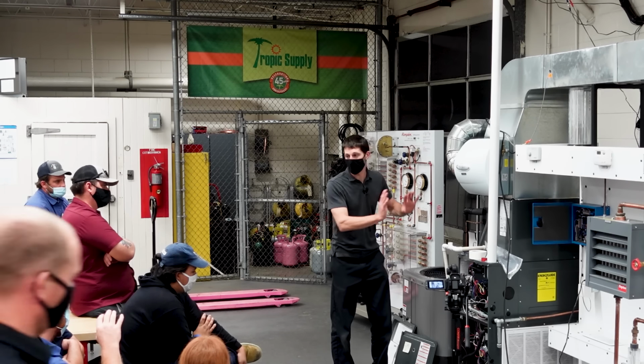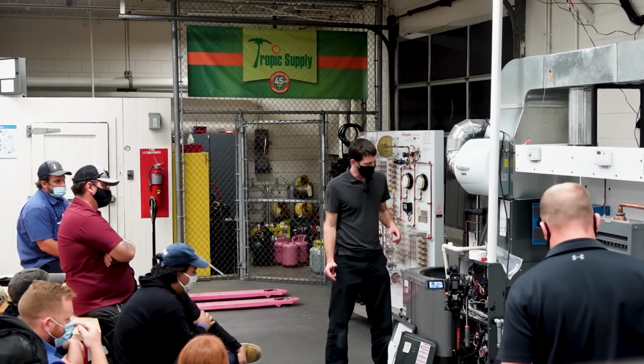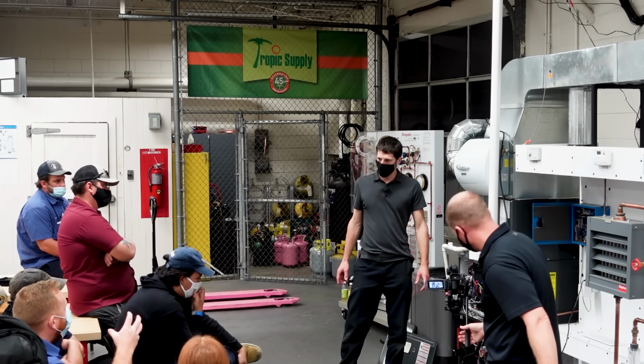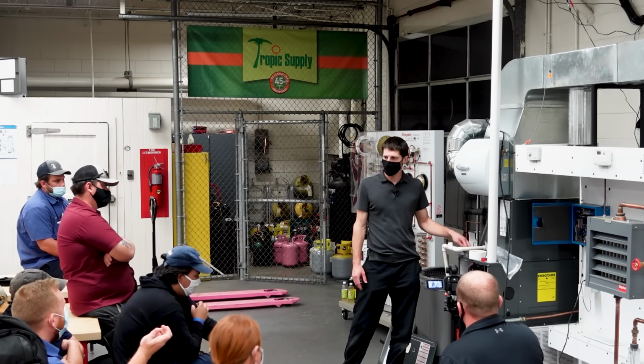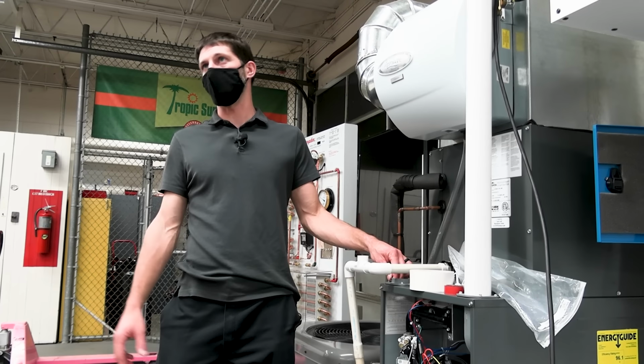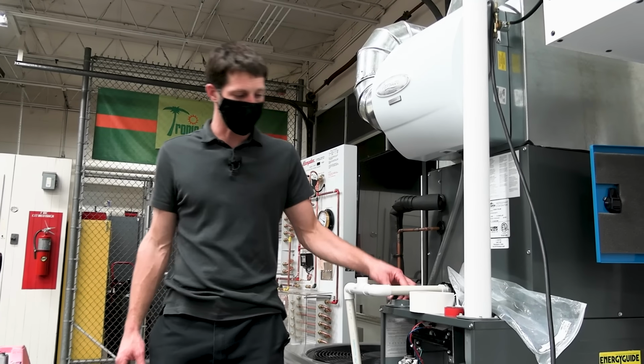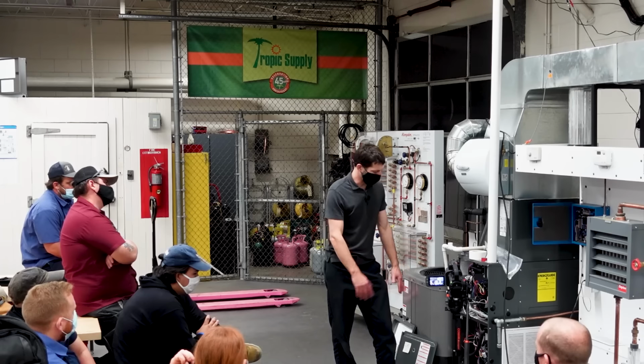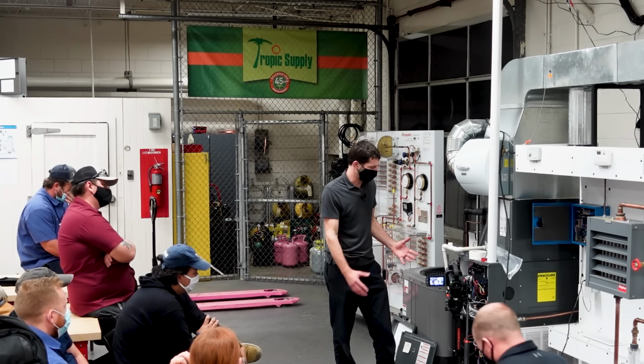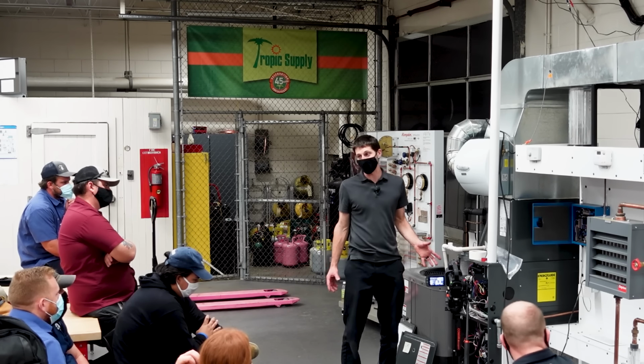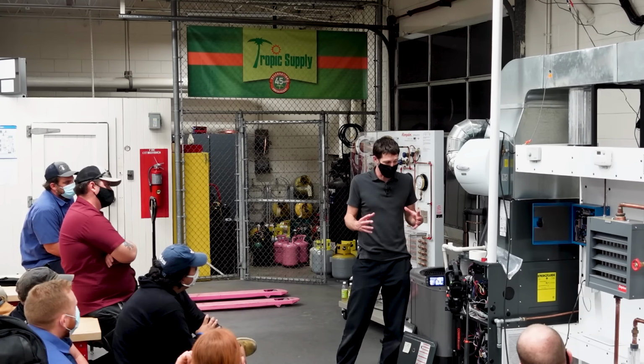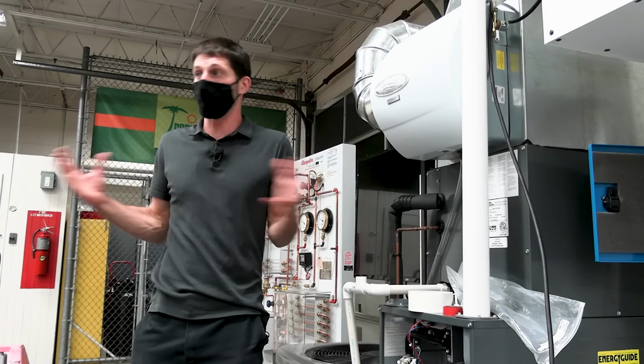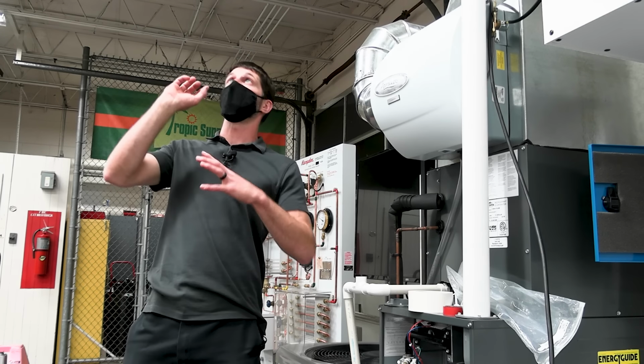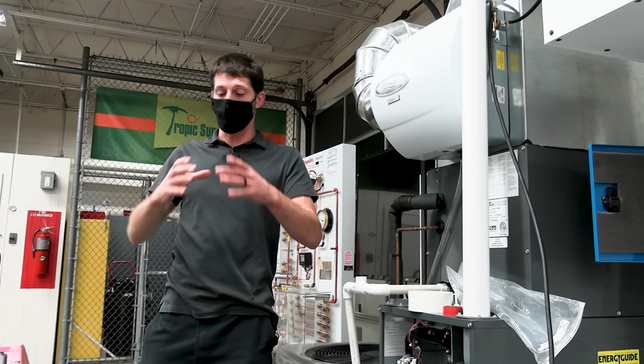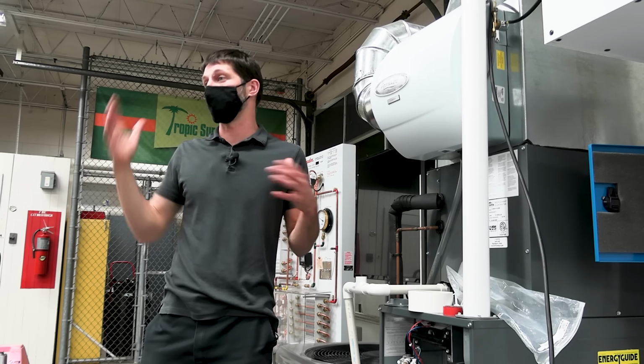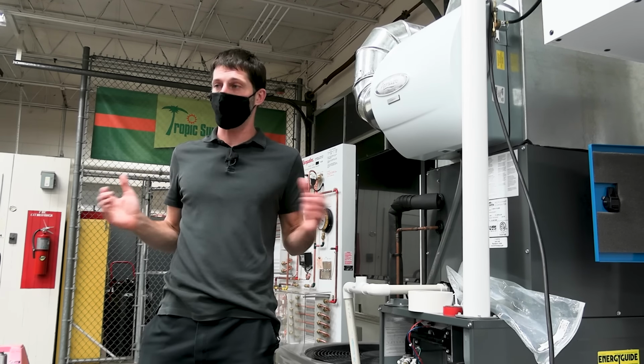Oh, if this was in a closet? Yeah. Yes. So it doesn't create that negative pressure in there, right, which then would kill the flame. Yes. Yeah, if you don't have good combustion air, the flame is not going to be efficient. It's not going to work really well. But it will get that. It will turn that into negative pressure, and it will pull it from outside somewhere. It will steal it from somewhere through a crack in the recessed ceiling light or whatever from the attic. There's going to be somewhere where it's going to pull air from.